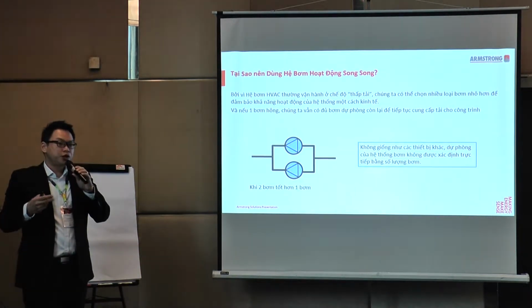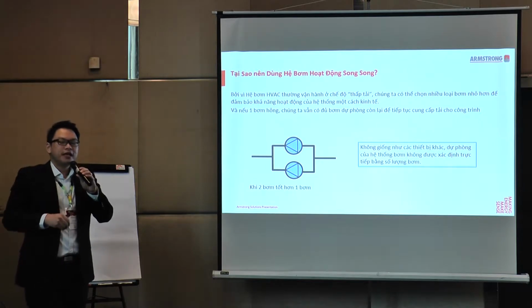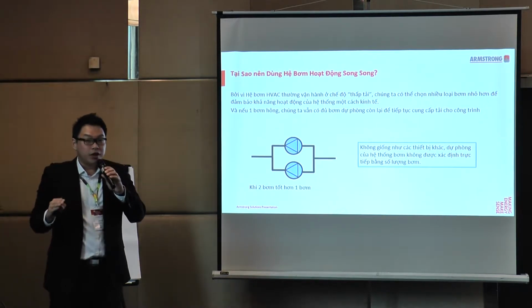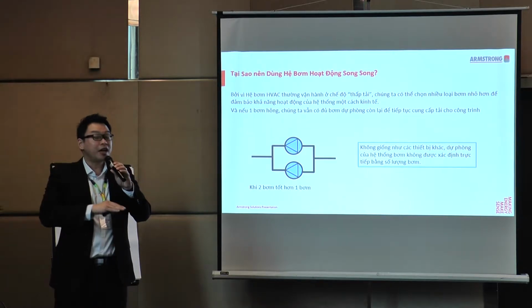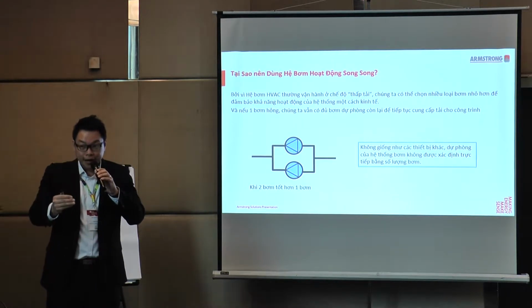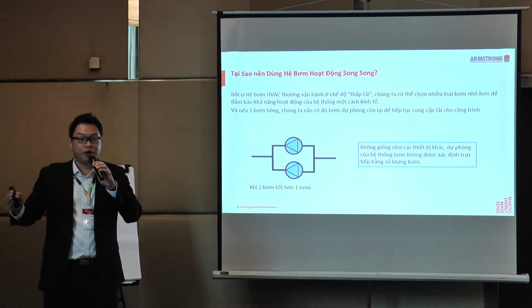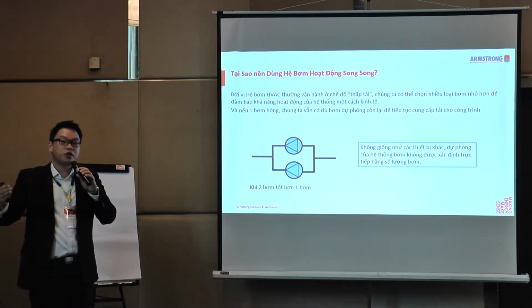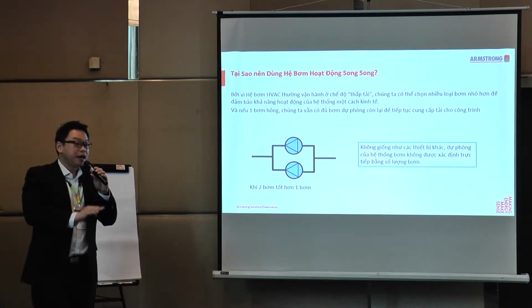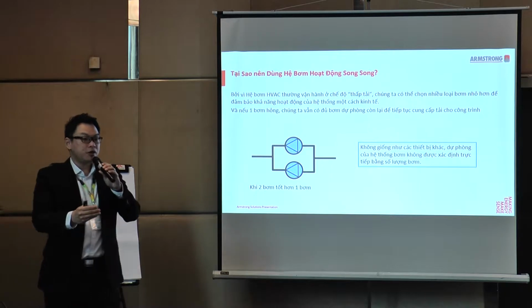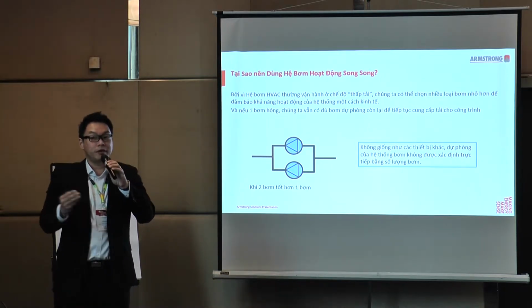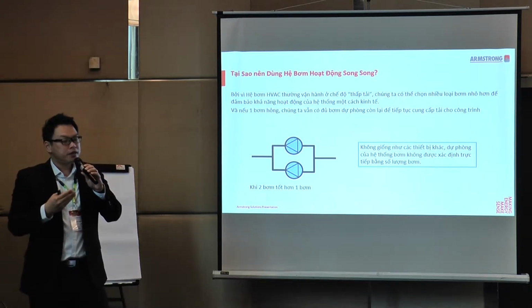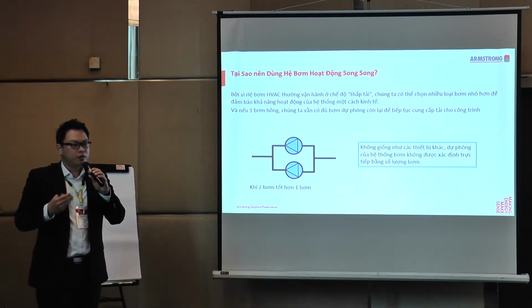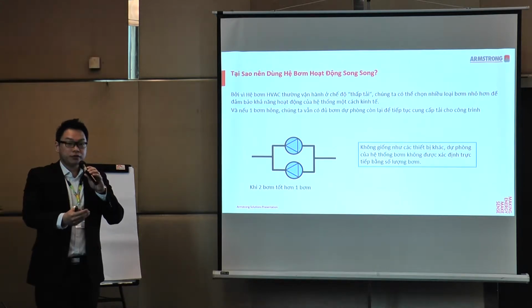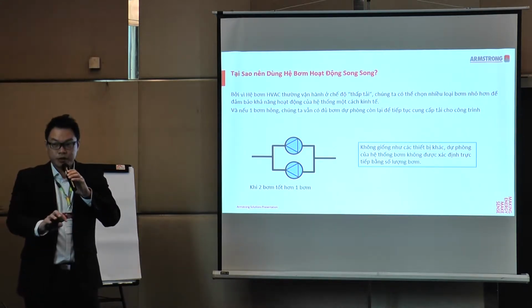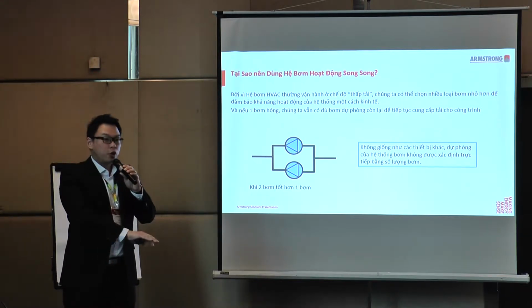The second concept I want to share with you, and again, you would have known, is that the HVAC industry is basically a part load industry. That means we are not operating at 100% of the design demand at all times of the day. Correct? If you were to do statistics over time, I would say that about 90% of the time we are only requiring 60% of the load. So what does this mean? When we size our pumps for part load, we can actually select smaller pumps to handle these lower flow requirements.